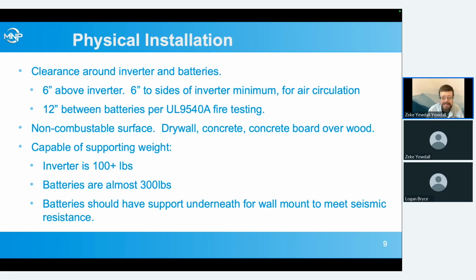If you're mounting batteries in 2 rows with an upper and a lower row, the batteries are not supposed to be solely supported by the wall mount to meet their seismic resistance. You can just hang them on there, but they're not going to be seismically rated if you do that. So you want to have a support underneath. What I use is a piece of 3-inch angle iron bolted solidly to the wall that the battery can rest on for some of the weight, if I need to get the seismic resistance on a row that's not sitting on the floor.